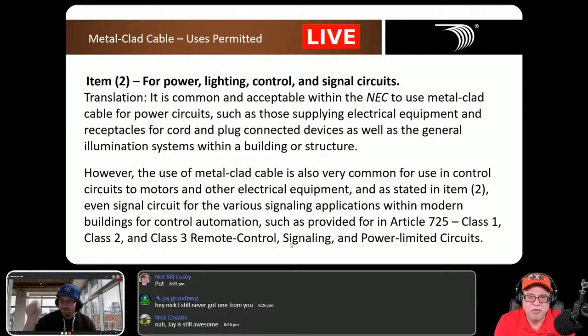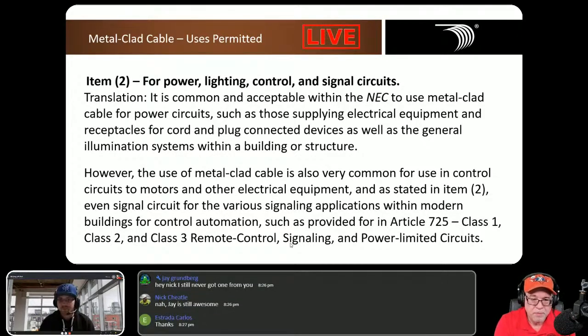The use of metal-clad cable is also very common for control wiring for motors, so it doesn't always have to be just power. It could be the control aspect of a motor control circuit, which wouldn't come out as power—generally a control system with a stop-start solenoid that pulls it in and locks it in, and once it's in it runs until it loses power, then it decouples. All of that could be an MC cable, and it's done all the time.